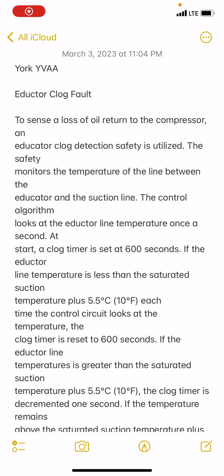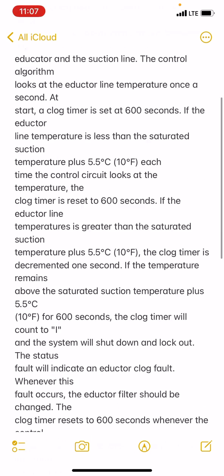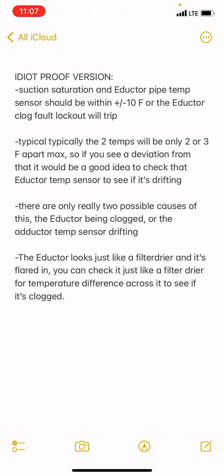This is a very common issue you're going to see with York chillers — it's an eductor clog fault code. I saw this today looking at a York YVAA. This is my version: suction saturation temp and eductor pipe temp sensor should be within plus or minus 10 degrees, or the eductor clog fault will lock that circuit out.